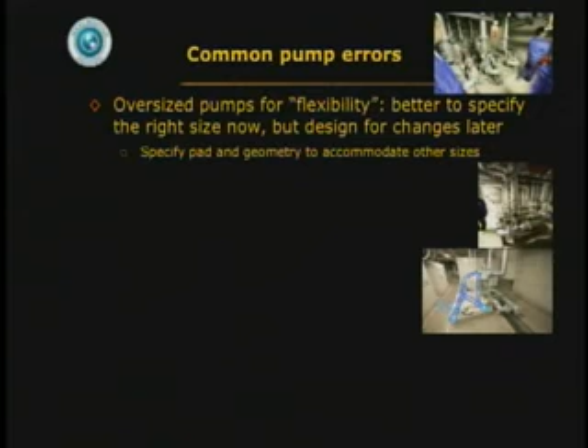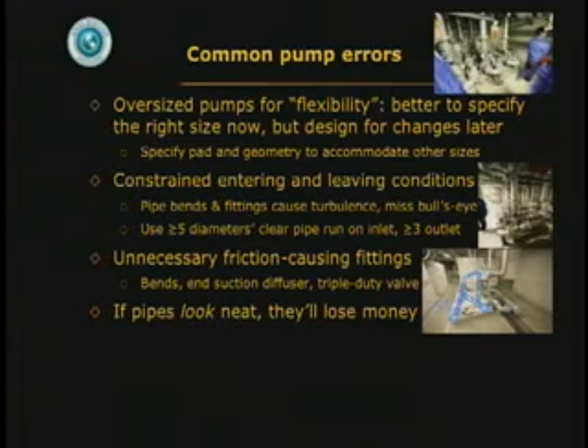Common pump mistakes: oversizing for flexibility. Well, make the pump the right size for what you got and design it so it's easier to put in a bigger one if you need to later. Make sure you have at least 5 diameters clear pipe run on the inlet, at least 3 on the outlet, so that the flow will be laminar enough for the pump to run as it's supposed to. Get rid of unnecessary fittings. You very often see end suction diffusers, triple duty valves, and so on that simply shouldn't be there and usually disturb the proper flow in and out of the pump.